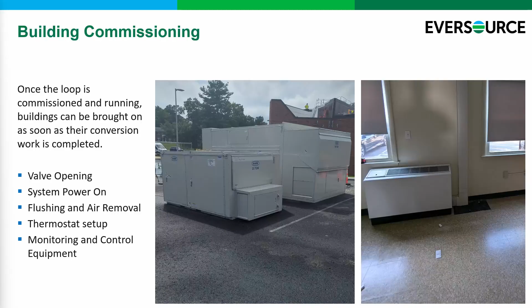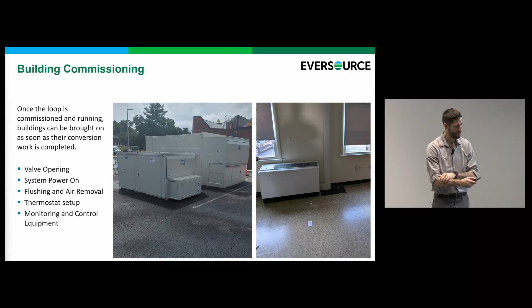One challenge I faced was that because we were using traditional gas contractors, they had a perception around how to handle valves on this system. In their mind, open valves are good—in a gas system, you open everything up and you've got flow, you're great. I had to go through the entire system and check every bypass valve, because 75% of them were left open. That means when I turn a customer's system on, they're not exchanging fluid with the loop, they're exchanging fluid with themselves, and their systems cool down quickly, shut off, and throw an error.